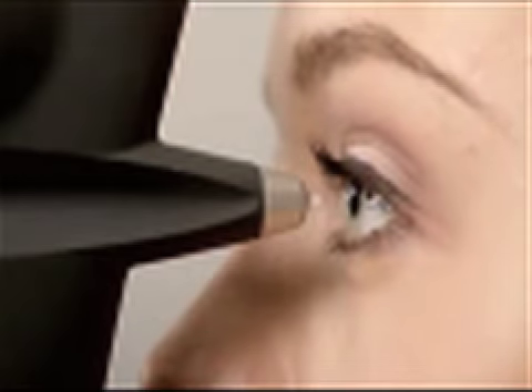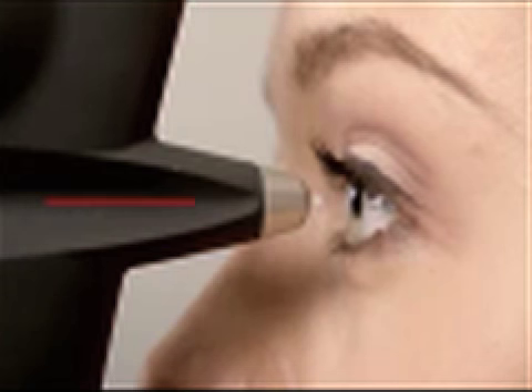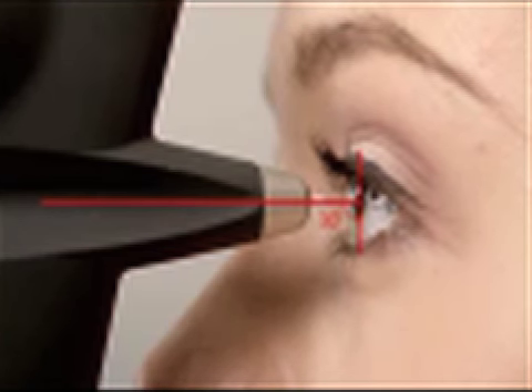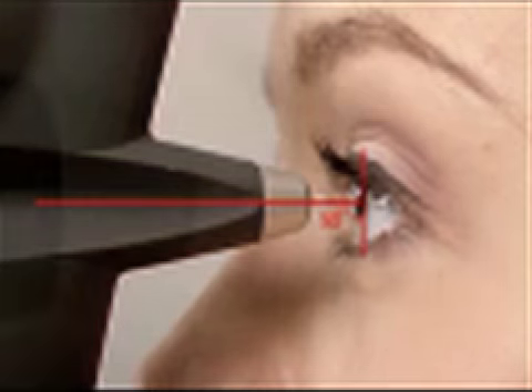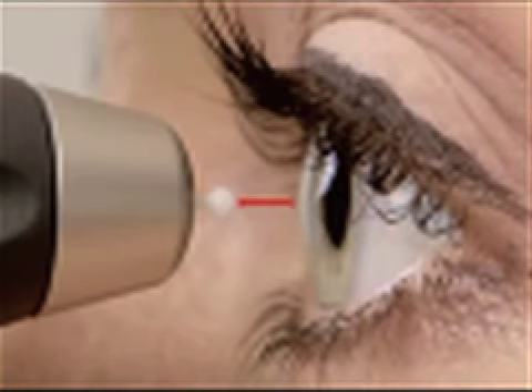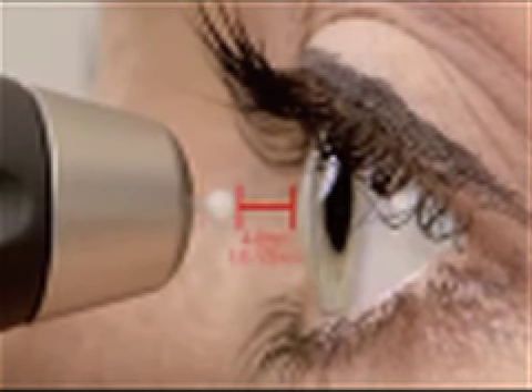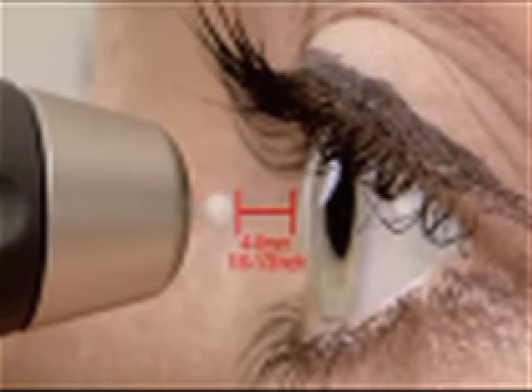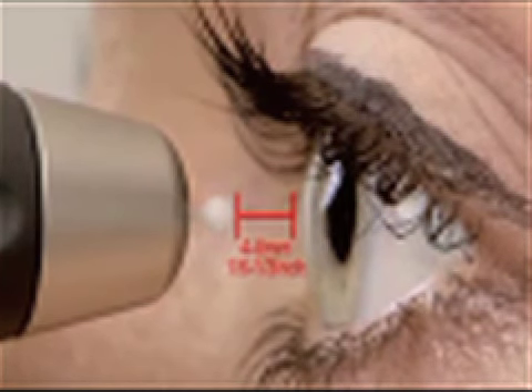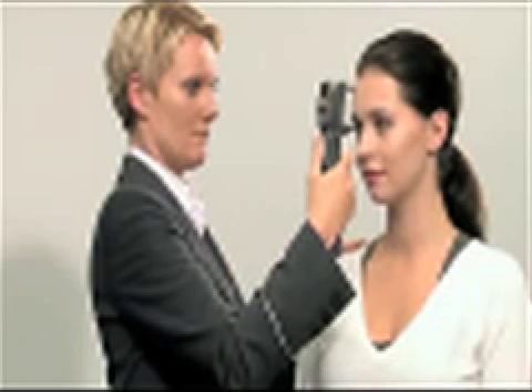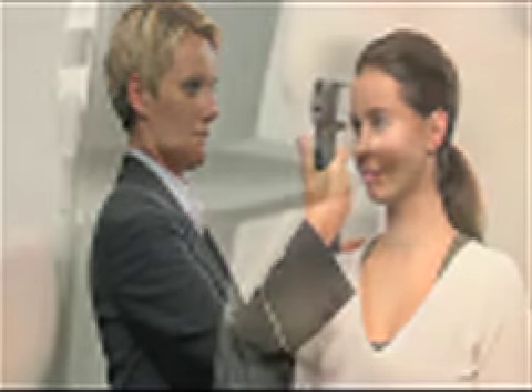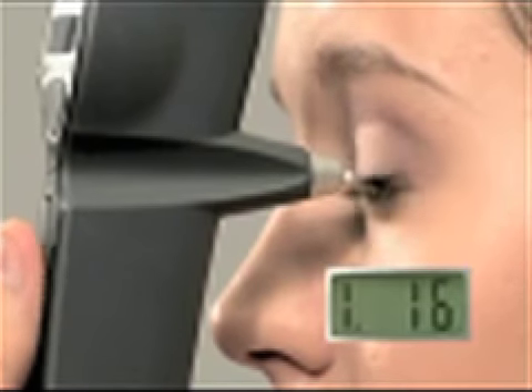Bring the tonometer near the patient's eye so that the central groove is in a horizontal position. The distance from the eye to the tip of the probe is from 4 to 8 millimeters, or 1/6 to 1/3 inch, respectively. Press the center of the measurement button lightly to perform the measurement. Be careful not to move the tonometer while measuring.